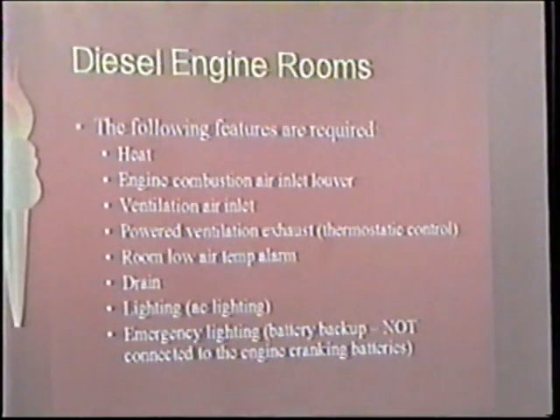Viking got hung up on a couple of these a few years back on a retrofit job where there was an existing engine application. They replaced the engine, and the fire marshal came back and said there's no ventilation there, no makeup, no combustion air. And all that stuff was not there the first time. All they did is take the old pump out and drop the new pump in, and so they get stuck. As contractors, you all need to be aware that the AHJ is probably going to look around and say, hey, this needs to be brought up.